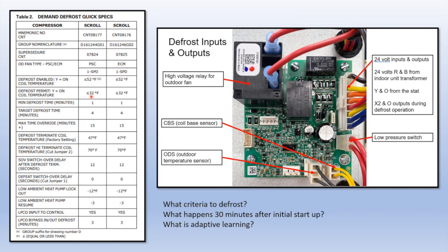And these are just to boost efficiency, because a defrost cycle is inefficient for the system as a whole, because it's running that outdoor unit essentially in reverse, taking heat energy from in the house and putting it in that outdoor coil. So you have a minimum defrost time of 1 minute. That means if it initiates a defrost, regardless of what the sensors say, they could say that it's over, it's going to continue to defrost for a minimum of 1 minute and a maximum time of 15 minutes, regardless of what the sensors say. The target time is 4 minutes. So it's going to adjust that delta based on the previous defrosts in order to target a 4-minute defrost time.